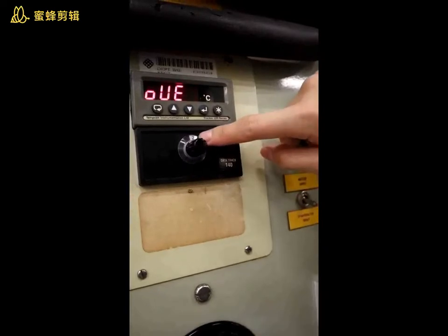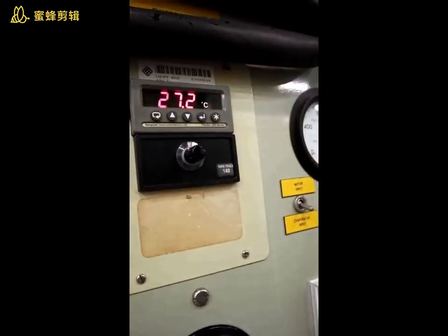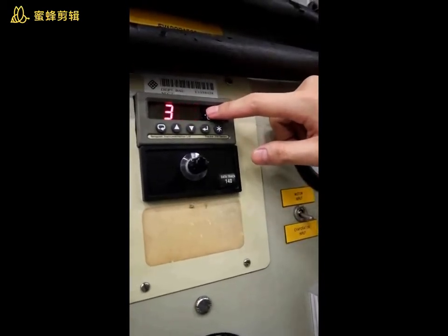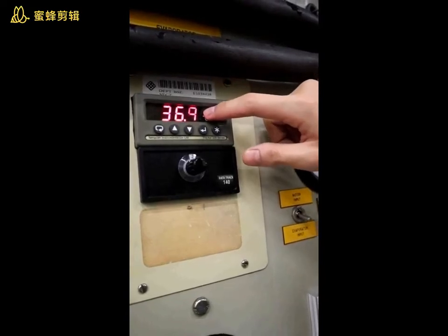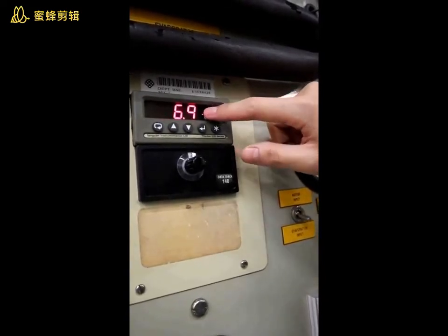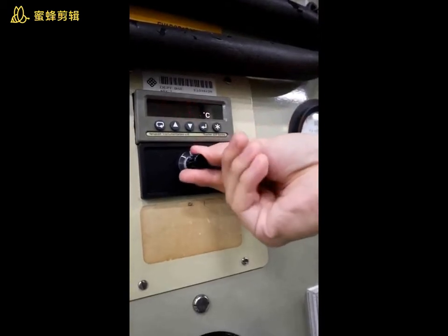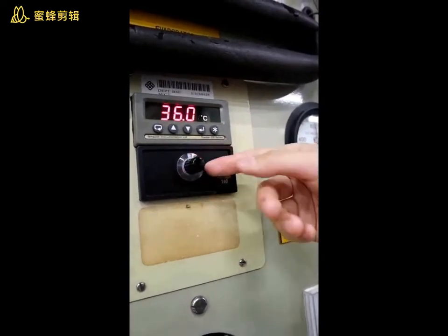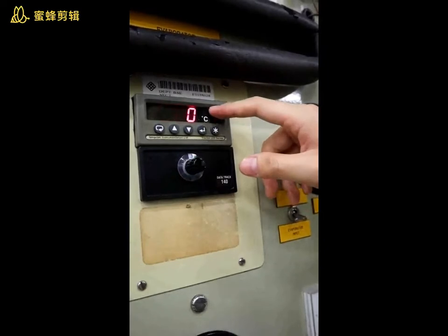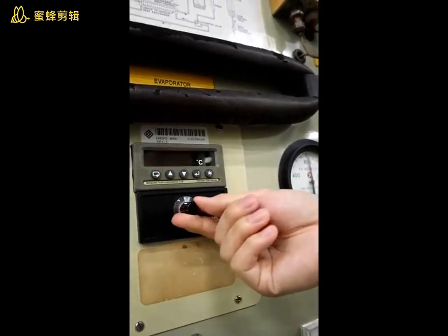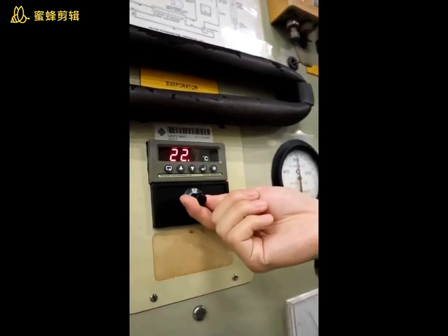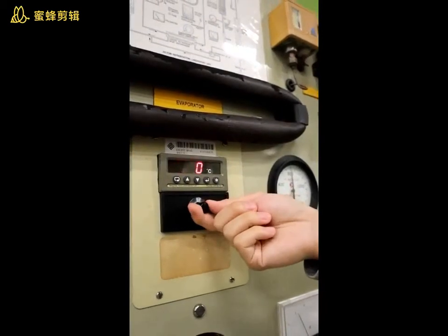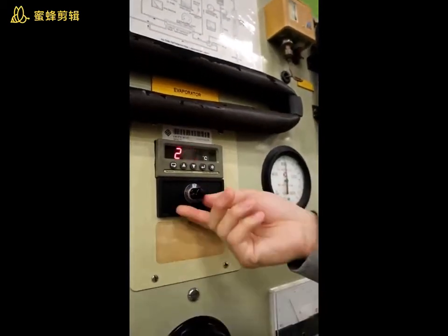Then we switch to point 2, which takes 4 seconds, and you can read the temperature of point 2, the refrigerant temperature coming out of the compressor. That is 6.9 degrees Celsius, and then the temperatures at points 3, 4, and so on. In each step of the experiment, we have to record these 7 temperatures, pick out the useful ones and mark them on the diagram.